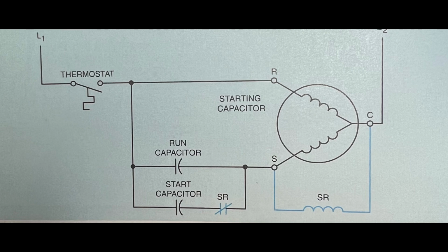Open case motors generally use a centrifugal switch to perform this function. But hermetically sealed motors generally depend on a potential starting relay. The potential relay operates by sensing the increase of voltage induced in the start winding when the motor is in operation. The coil of the relay is connected in parallel with the start winding of the motor. A normally closed start contact is connected in series with the starting capacitor.